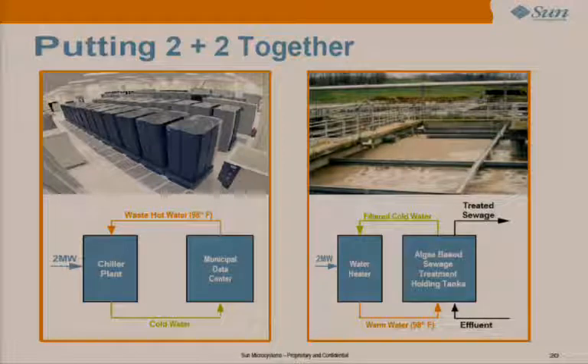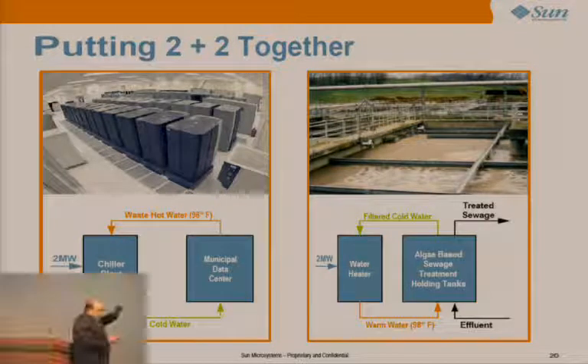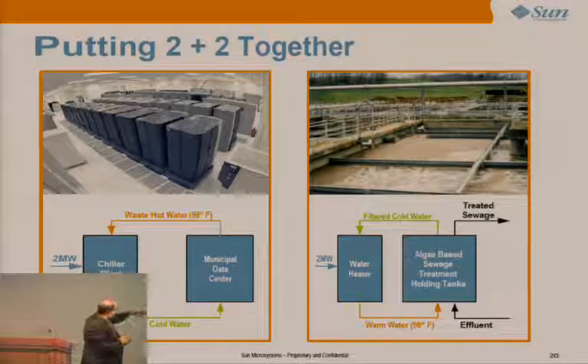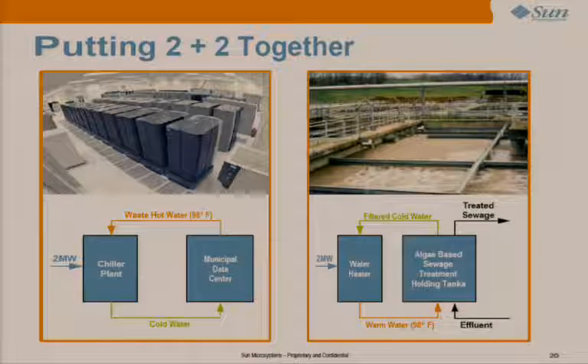We have a customer that is a municipality - I can't name the city, but it's in the state of Indiana. They used to have their own municipal data center where they had waste hot water at 98 Fahrenheit that they fed to a chiller plant into which they pumped 2 megawatts of energy, getting the cold water back to feed into the air conditioners for the data center.